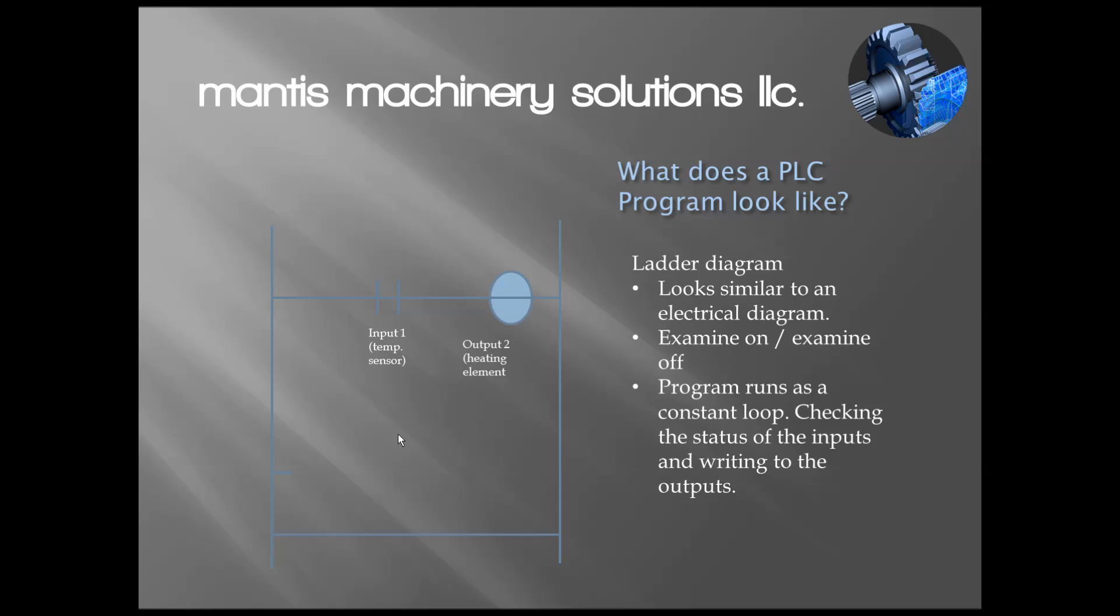The idea here is if input number one is made or high or if there's 24 volts on it, a condition exists that would cause this contact to close. It's going to complete this current path and turn on output number two. So it's really that simple. For this first rung, the only condition that needs to be made in order to create an output is to have an input on temperature on number one. As the temperature of whatever I'm trying to heat rises, it's going to remove that input here and open up this path, and the output is going to turn off.